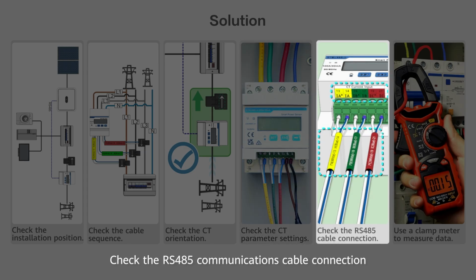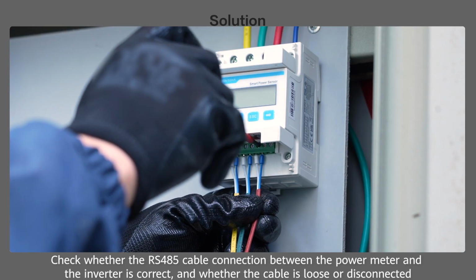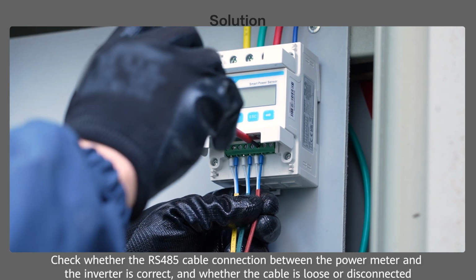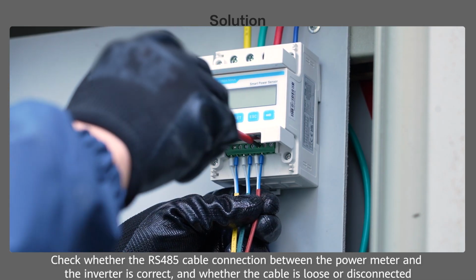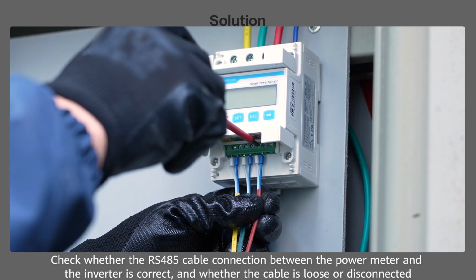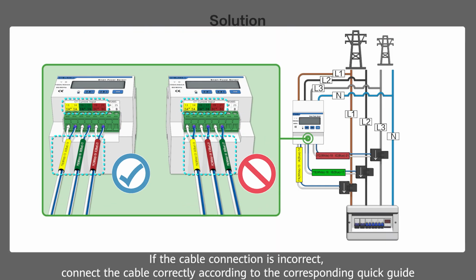Check the RS485 communications cable connection. Check whether the RS485 cable connection between the power meter and the inverter is correct, and whether the cable is loose or disconnected. If the cable connection is incorrect, connect the cable correctly according to the corresponding quick guide.